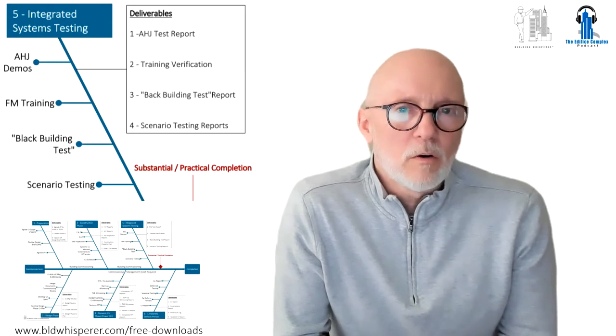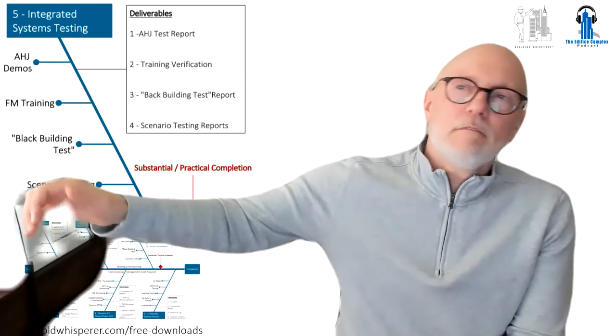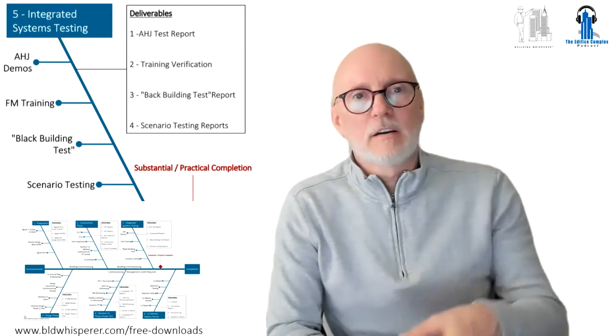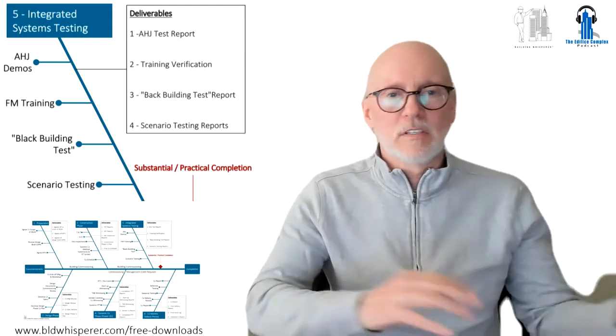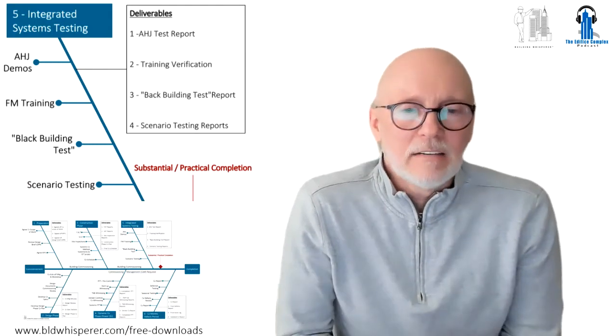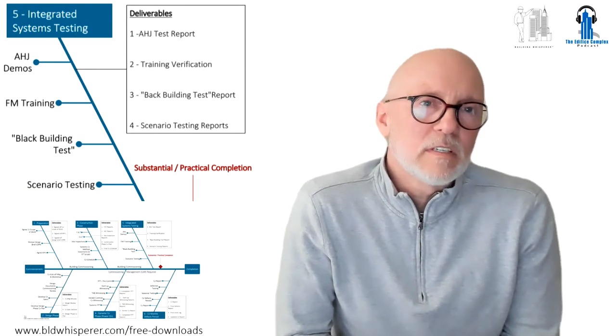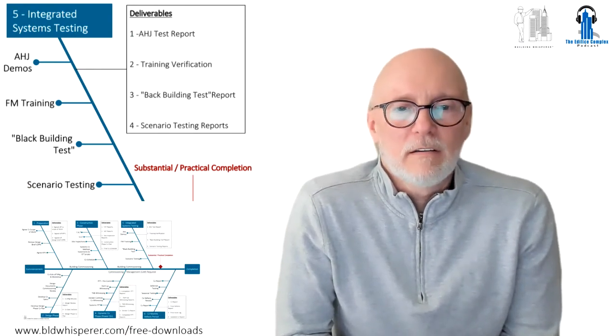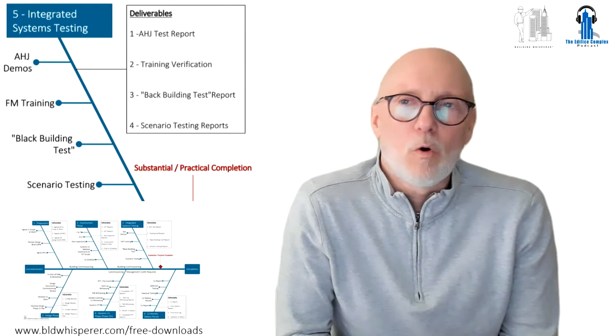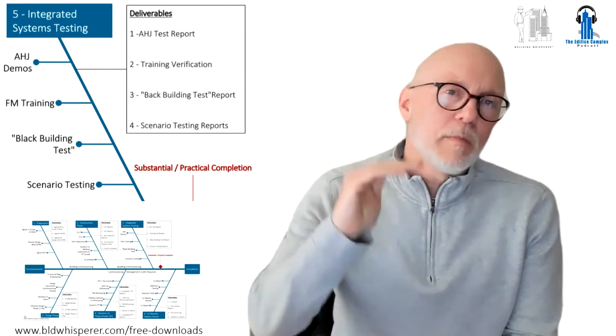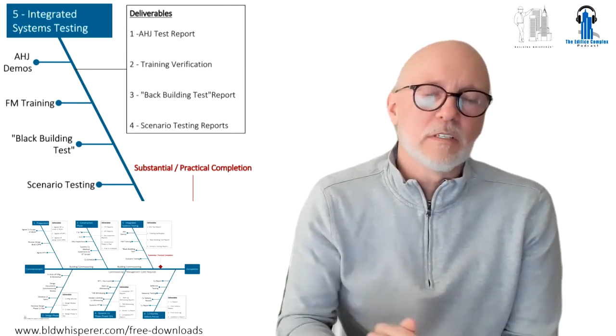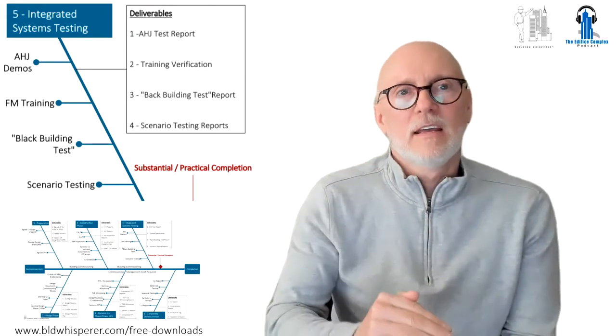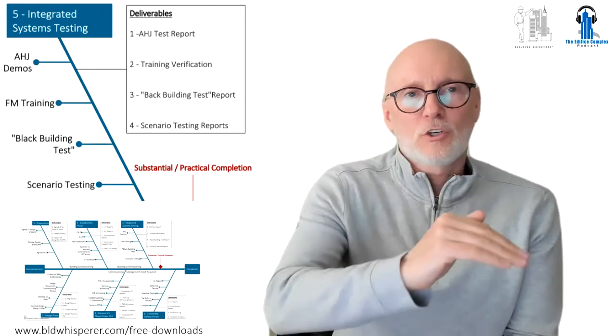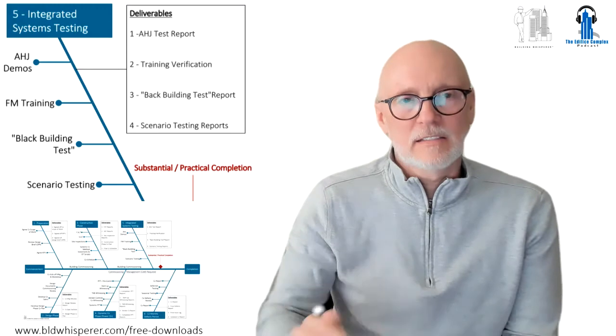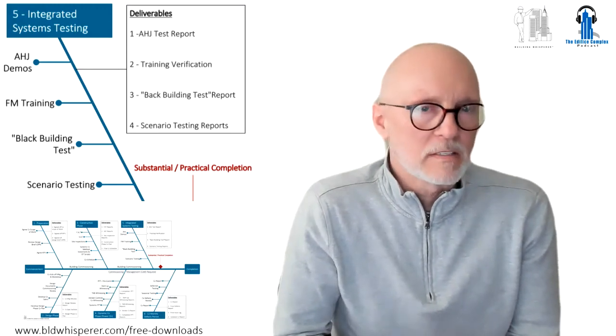You need to know: if I pull the fire alarm in the lobby, does the elevator ground, do your air handling units go off, does this happen, does that happen? So you need that. The other thing you need are test scripts - these detail all the tests you're going to do for the different modes of operation and different failure possibilities. That needs to be scripted out, the expected actions and reactions, then checked and tested to see if they happen, and all documented as results.